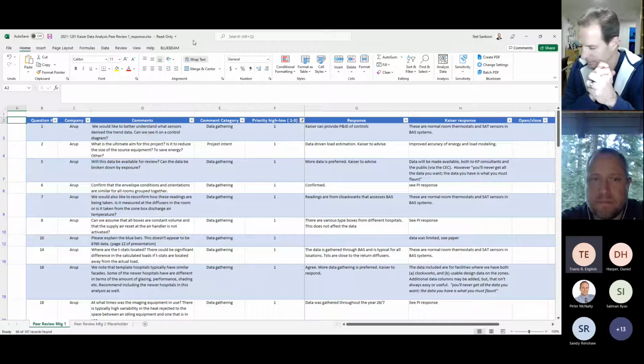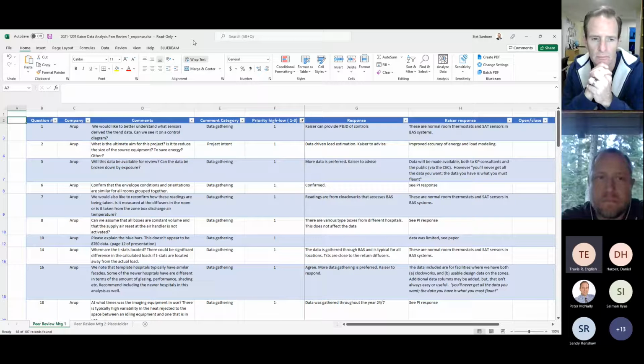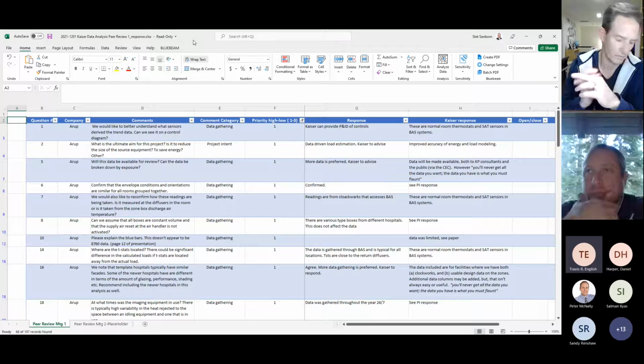I think what we're seeing in the data, though, is that anytime you have more than a couple rooms, the room-to-room diversity that our calculation methodologies would assume to be zero, whether we're doing TRACE and we put the same load profile into all the patient rooms, or we're doing EnergyPlus and put the same load profile into all the patient rooms, the idea that room-to-room diversity is zero, we're definitely seeing that to be false. Mm-hmm. And to the point where, when we first looked at them, they looked like rather shocking numbers.